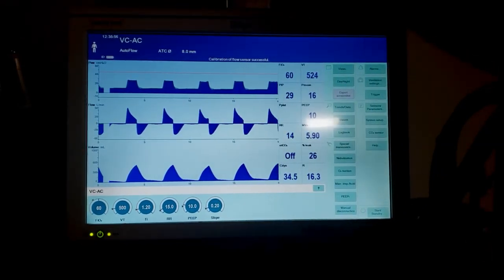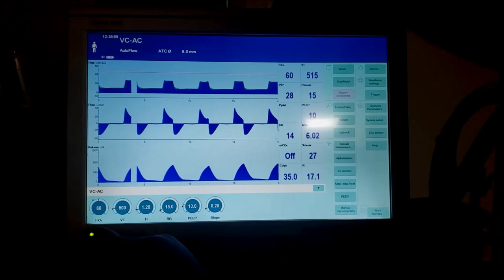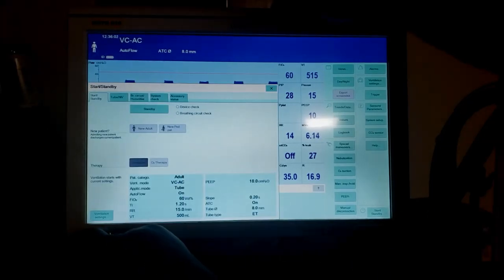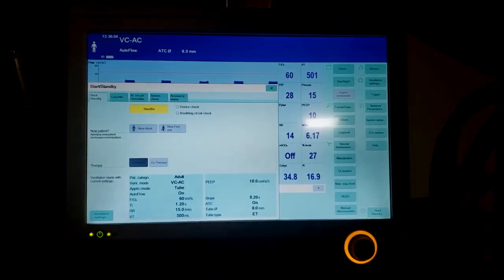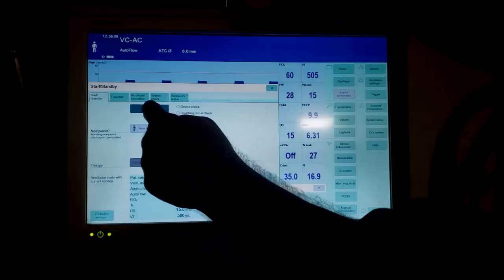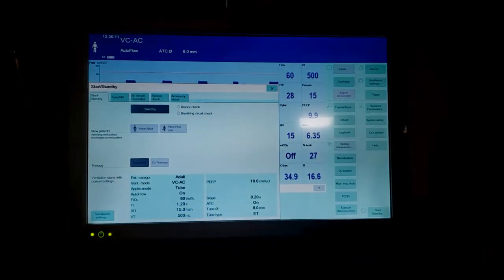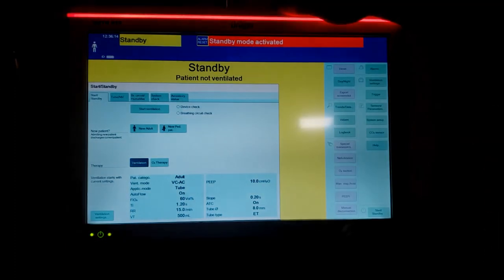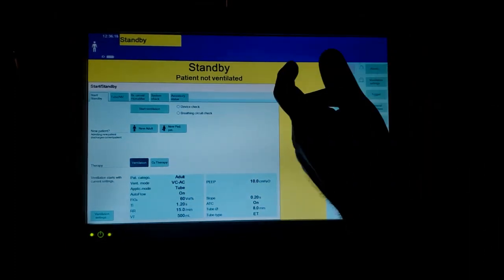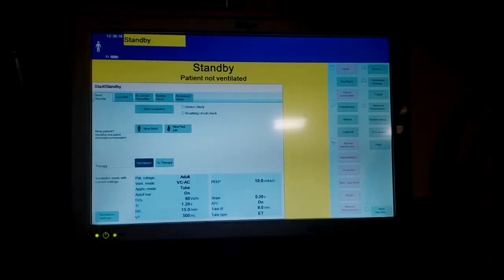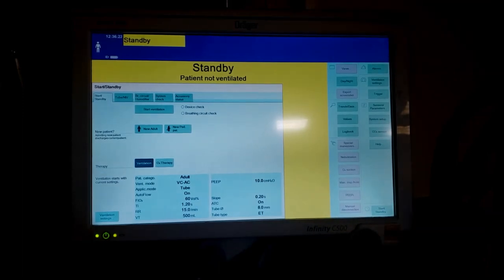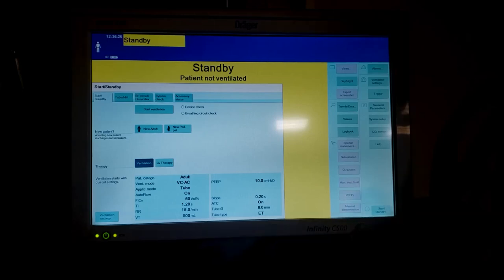The last thing you need to know: on/off switch. Turn it on/off here. The standby button - it will not let you just put them in standby. You have to touch, like this case you touch it, confirm it here. They go into standby. Obviously you don't do that with a patient on it. Then I reset the alarm, and that is a quick rundown of how to run a Drager v500. Thanks for watching.